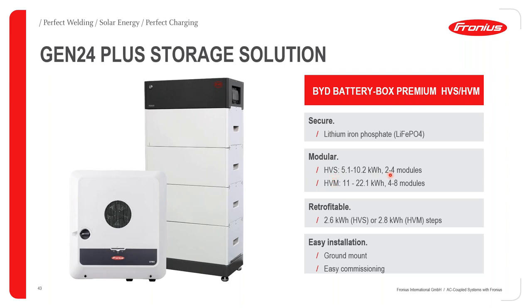With the HVS variant, we start from 2 to 4 modules, and that will give us an energy storage of between 5.1 to 10.2 kilowatt hours. So each one of these gray blocks represents around 2.56 kilowatt hours. When we add them in series, we build up the capacity. Then having a look at the HVM, which starts from 11 to 22.1 kilowatt hours, it starts from 4 to 8 modules.